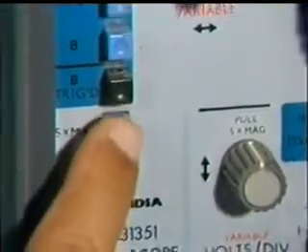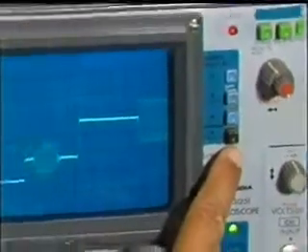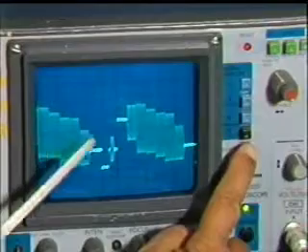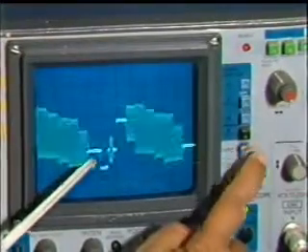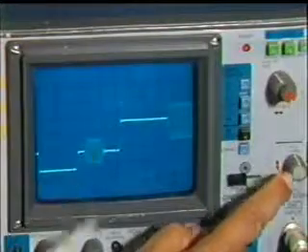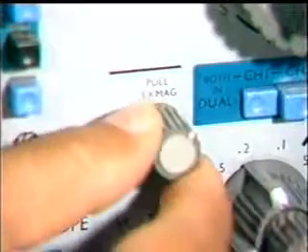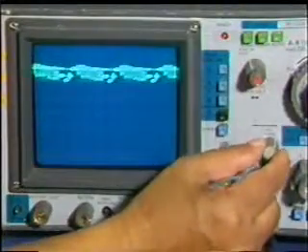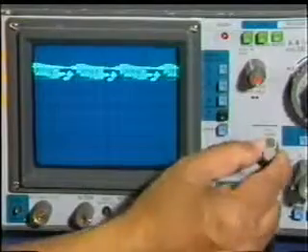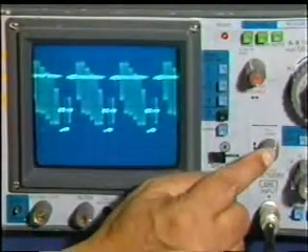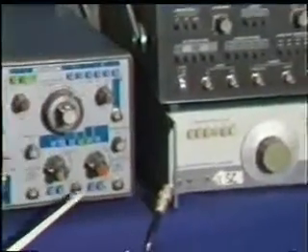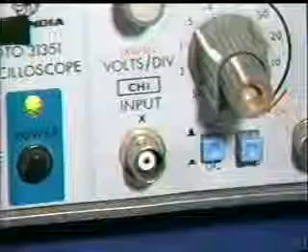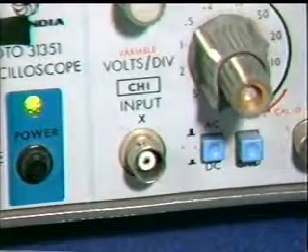When the five-times magnification knob is pushed, the displayed signal is spread five times in the horizontal. When this knob is pulled out, the vertical amplification gain is increased by five times, meaning the vertical sensitivity is increased five times. In the pressed position, it acts as a vertical positioning of the signal or beam.